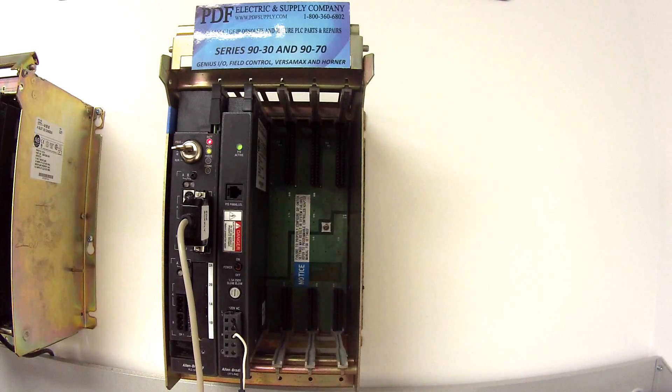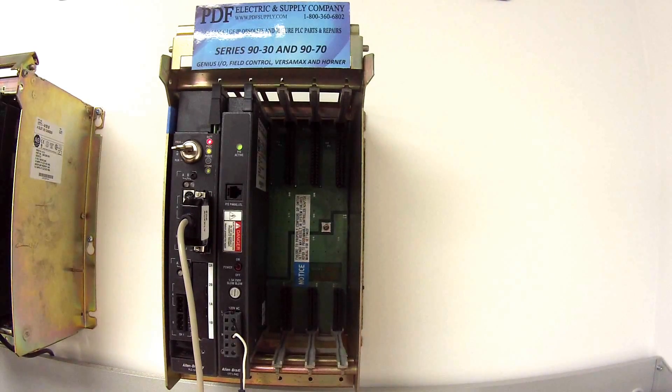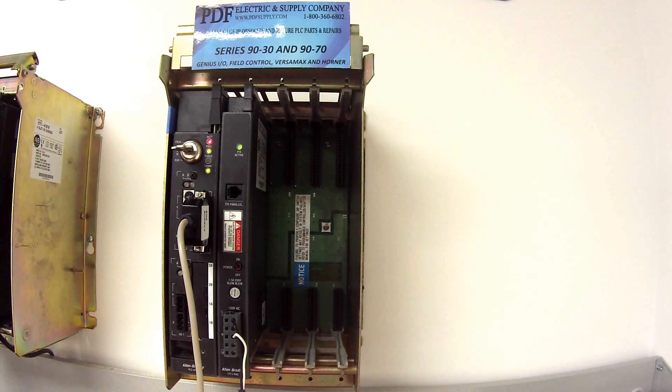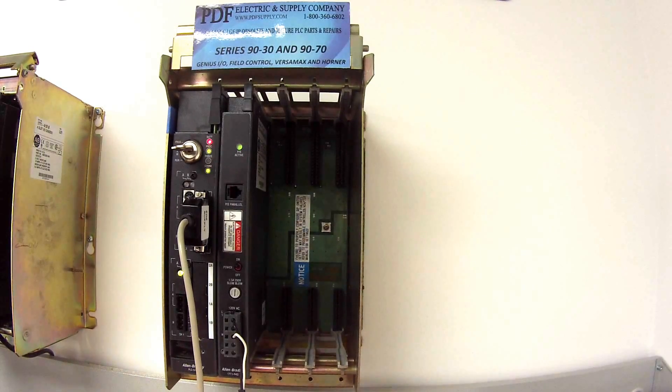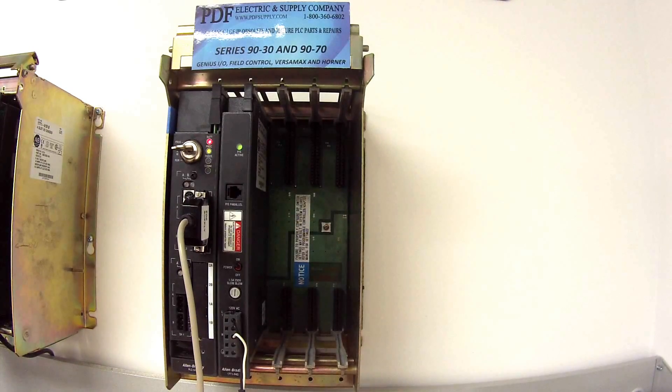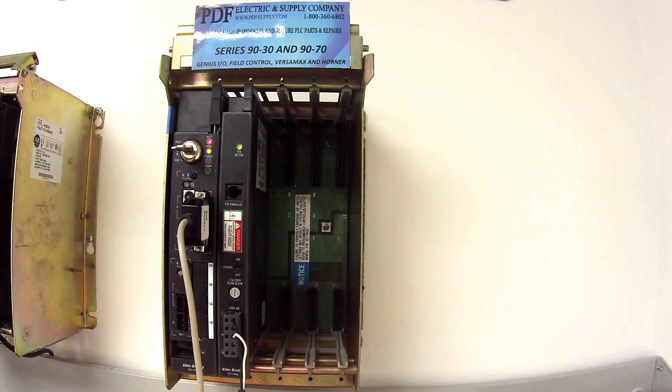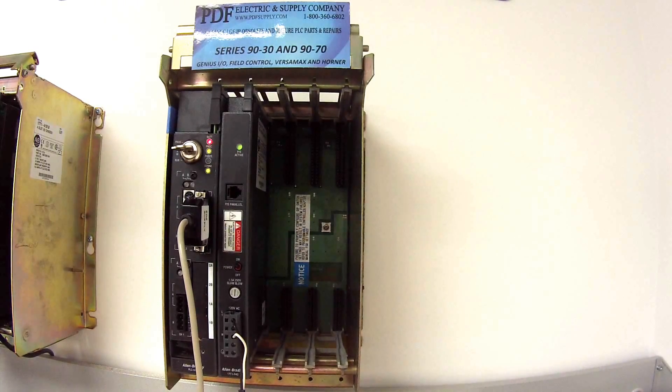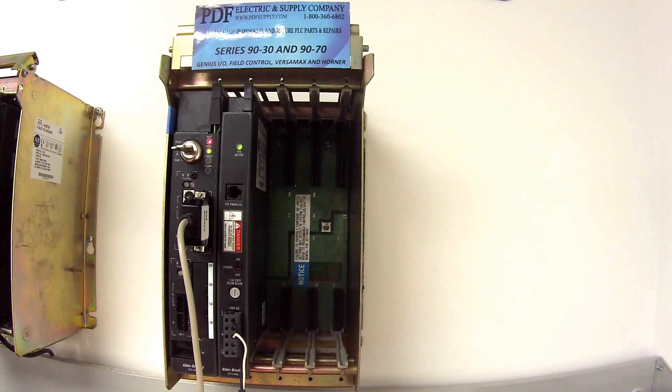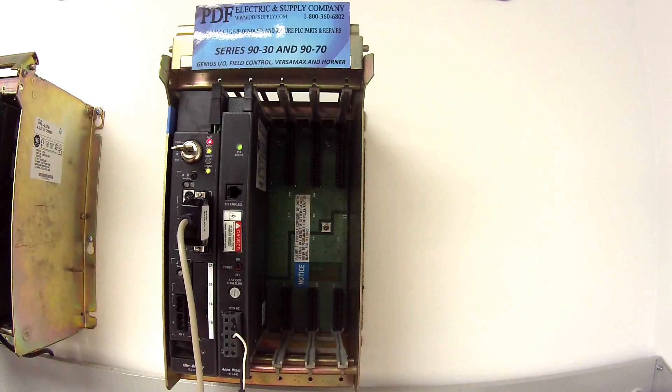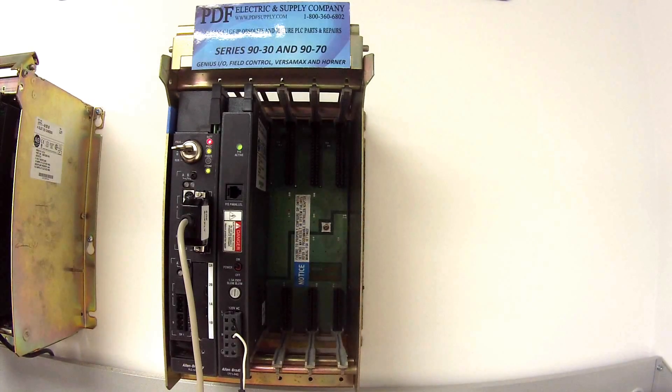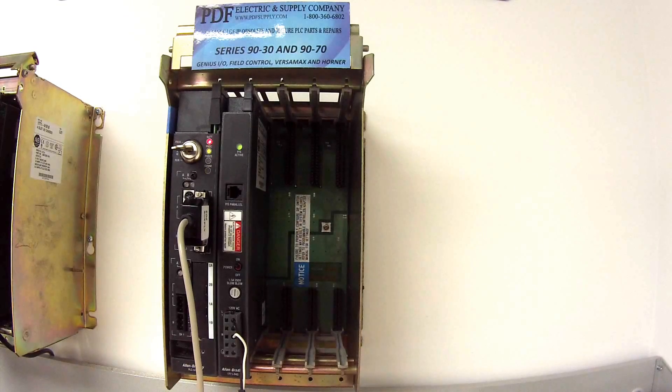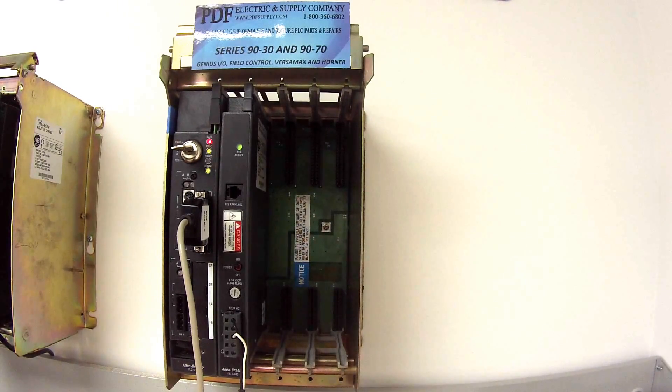And what I'm going to do is go over to errors. So you'll have a window that pops open that says file S2 status. And then there'll be tabs at the top, main, MCP, scan times, math, switches, errors. I'm going to go to errors and find out if there's any errors, major errors, error codes. Now I'm going to find out if there are any errors, what they are, what they pertain to. And if it's nothing major, I can go ahead and click a button that says, at the bottom left it says clear major errors if you are having a problem.